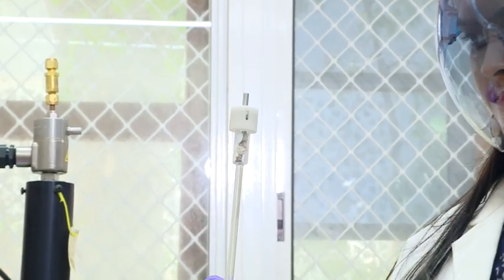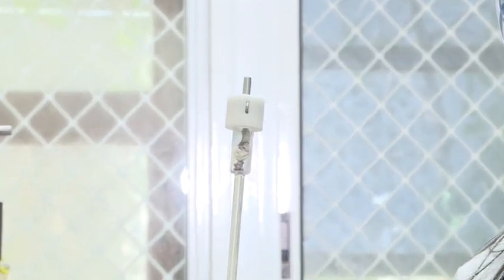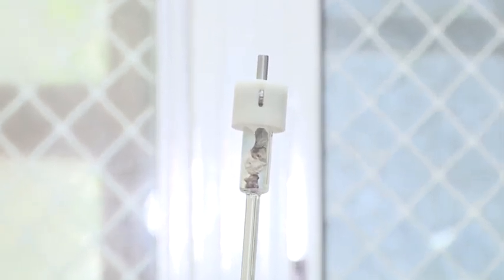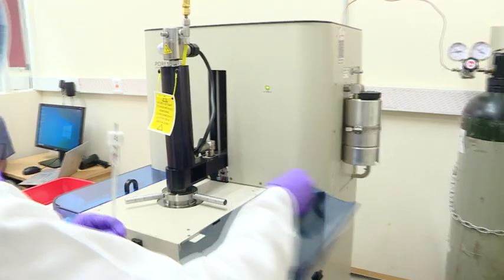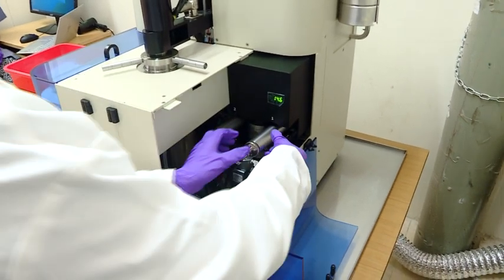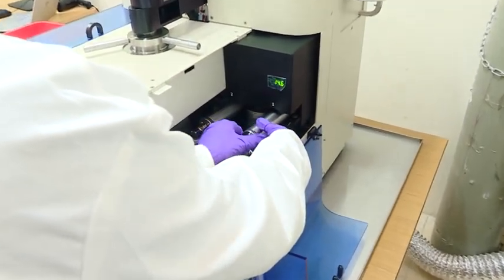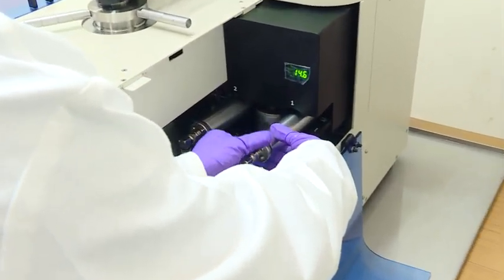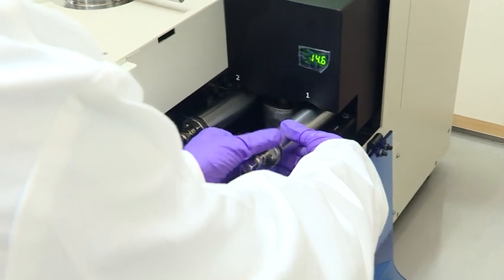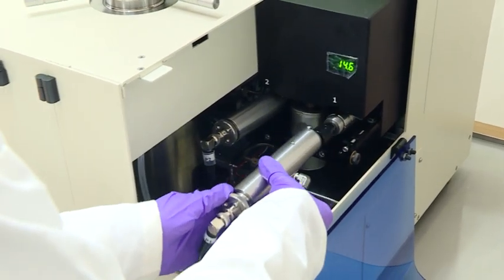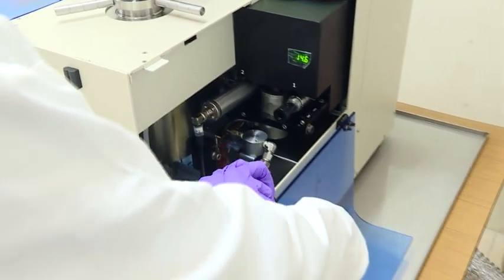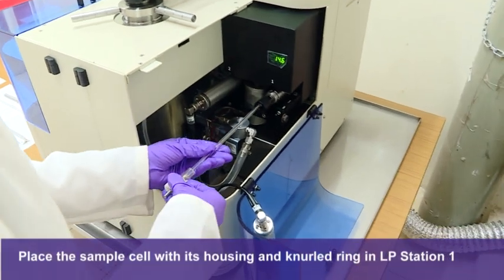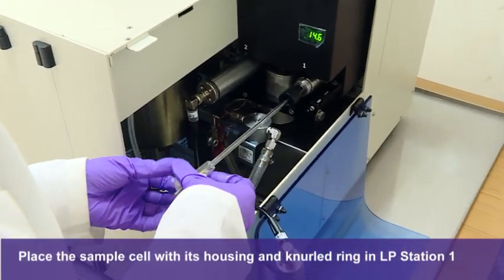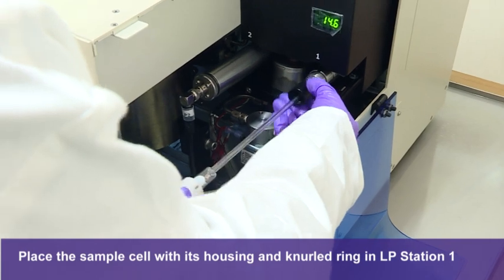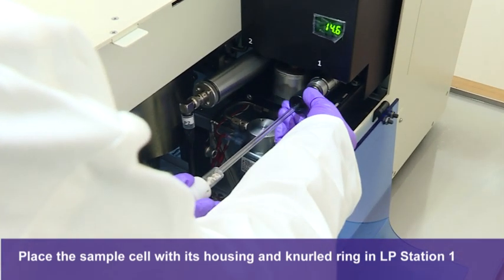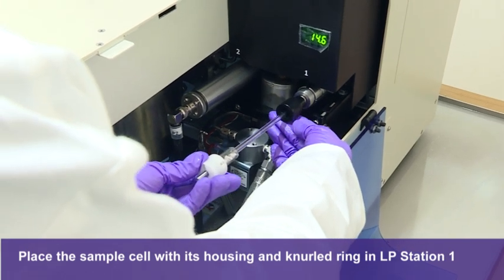The sample is ready to be tested in the low pressure system. So for that, the low pressure chamber needs to be opened. Now place the sample cell with its housing and knurled ring in LP station 1. We have to insert the cell very carefully.